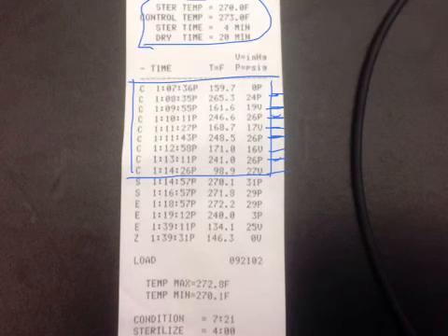The 4-pulse, you may hear, you may not, it's not general terminology, but essentially what that means is it took 4 pulses of steam in this prevac in order to condition. So this machine was set to do the four pulses of steam in order to prep the chamber. Then we're going to switch to sterilization mode. And so once that last vacuum is released, then steam is released into the autoclave, allowing it to go up to the 270 degrees above 27 psi.